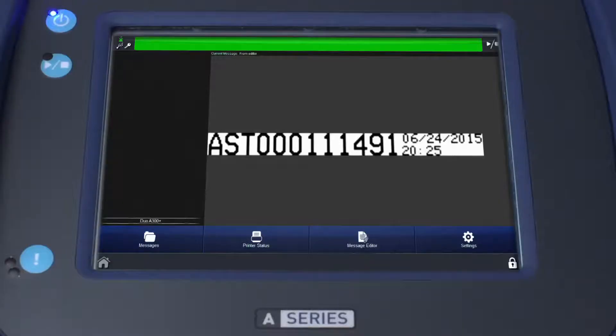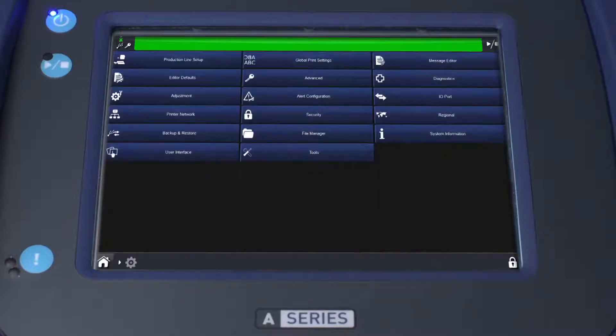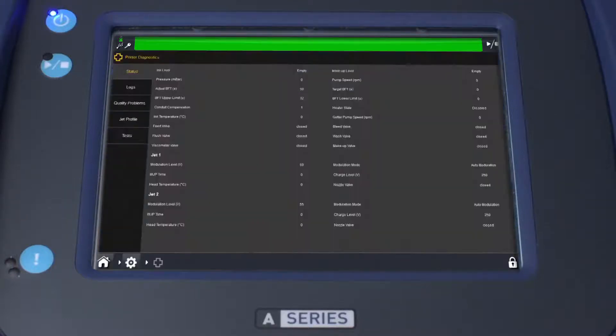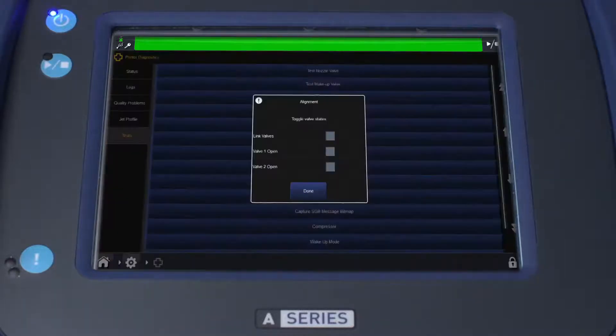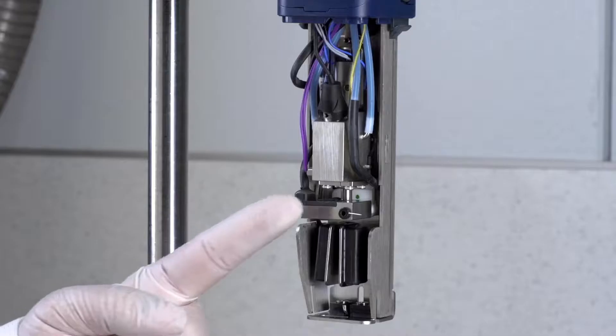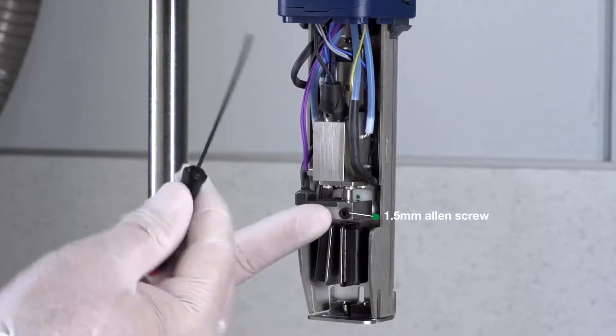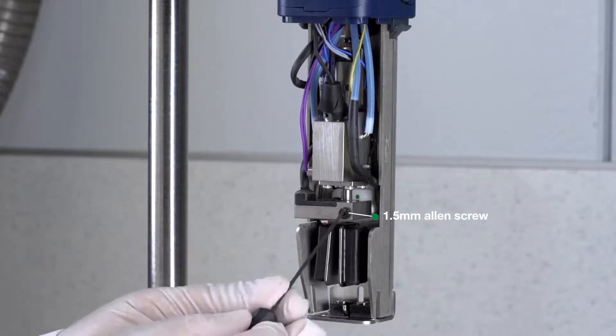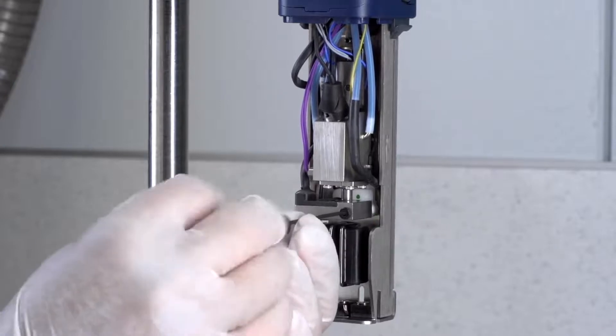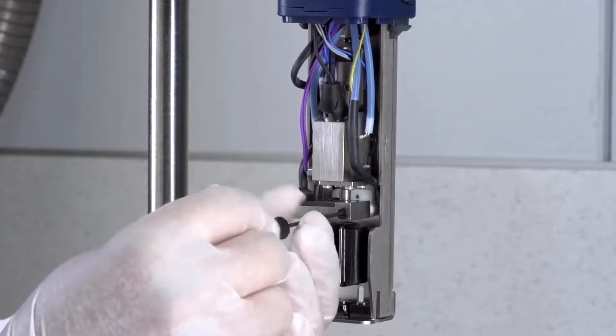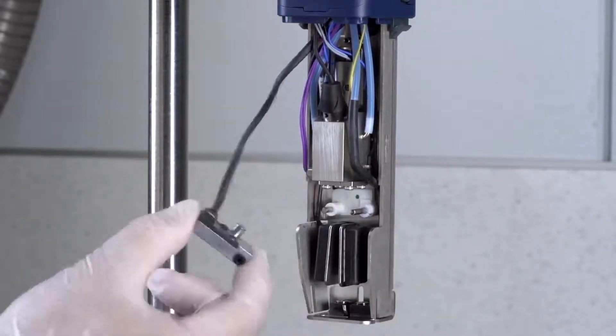Again from the front panel, select the Settings button, then Diagnostics, followed by Test on the lower left-hand side of the screen. Select Alignment, then select the checkmark to start the jet. Now remove the charge electrode by unscrewing the 1.5mm allen screw on the right-hand side. Carefully slide the charge electrode out of the way.